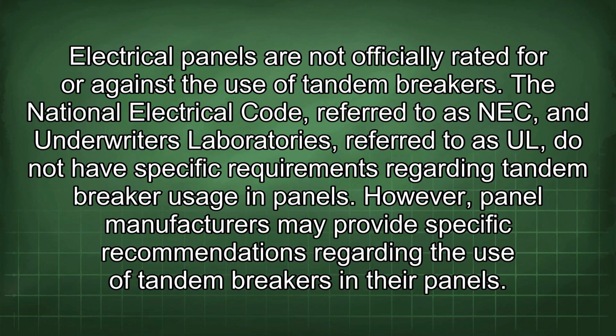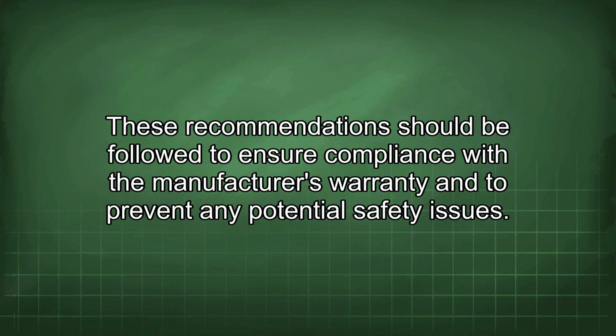Electrical panels are not officially rated for or against the use of tandem breakers. The National Electrical Code, referred to as NEC, and Underwriters Laboratories, referred to as UL, do not have specific requirements regarding tandem breaker usage in panels. However, panel manufacturers may provide specific recommendations regarding the use of tandem breakers in their panels. These recommendations should be followed to ensure compliance with the manufacturer's warranty and to prevent any potential safety issues.